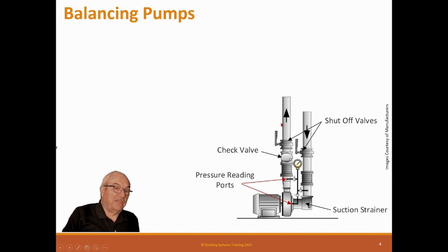And the reason I bring that up is because the pump manufacturers, in their infinite wisdom trying to sell stuff, created triple duty valves. The triple duty valve takes the place of a shutoff valve and the check valve and a balance valve all in one valve. And they sell them to contractors saying this will save you money because you only have one set of flanges to do. You don't have three sets to do, only one. It'll save you a bunch of money. But the truth is, we don't need them. We don't want them.